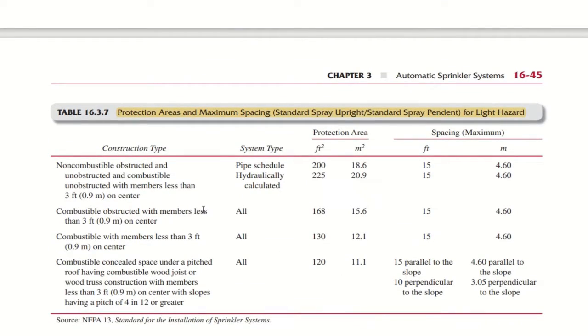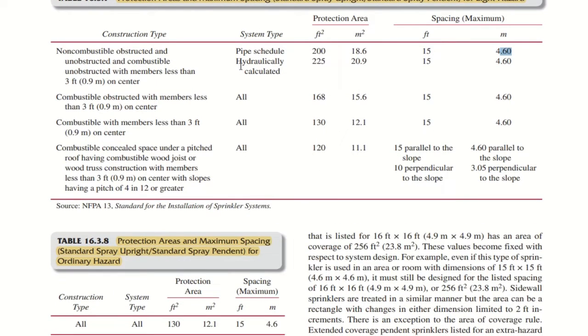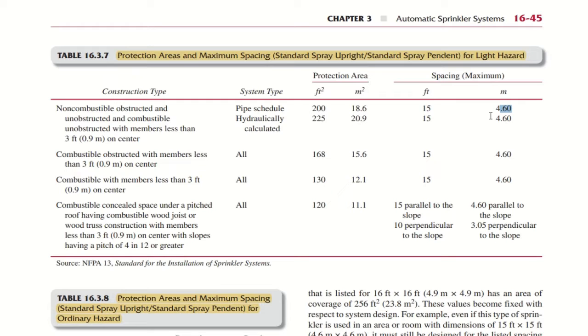Okay, so here you have one more table 16.3.7. Here it says protection areas and maximum spacing for standard spray upright or standard spray pendant for light hazard occupancies. Here for example you have non-combustible, obstructed and unobstructed, and combustible unobstructed with members less than 3 feet on center. For example, if you are going ahead with the pipe schedule method or hydraulic calculation method, there is the protection area to be considered. As a thumb rule for pipe schedule, you can go ahead with 18.6 square meter protection area for one sprinkler, and the distance between sprinkler to sprinkler for pendant or upright will be 4.6 meters. For hydraulically calculated methods also, the protection area or the coverage area of one sprinkler can be 20.9 square meter, and the maximum spacing shall be 4.6 meters.